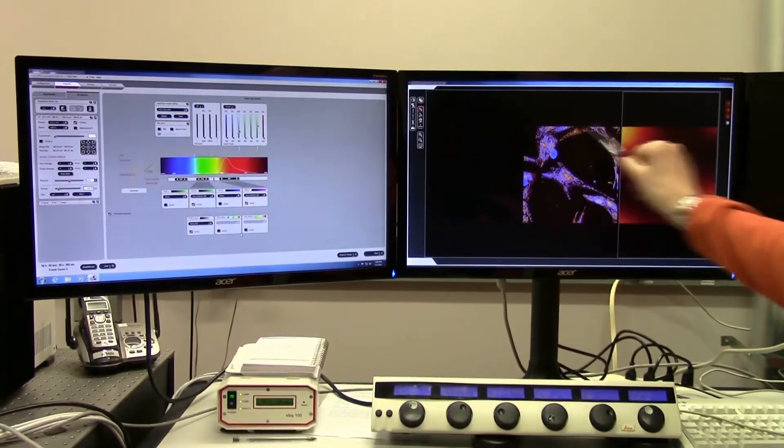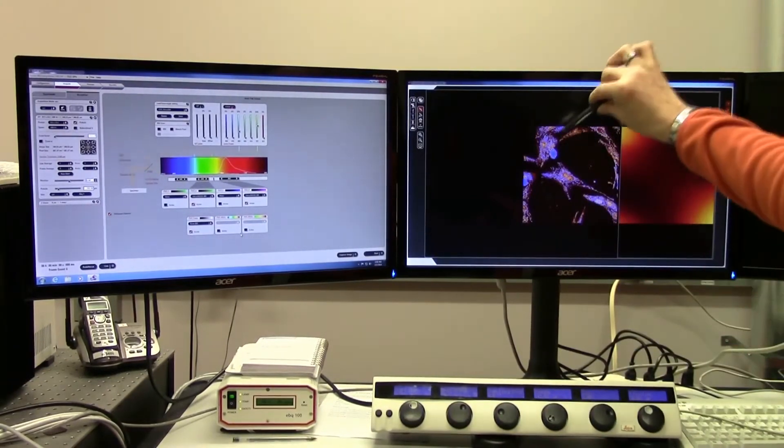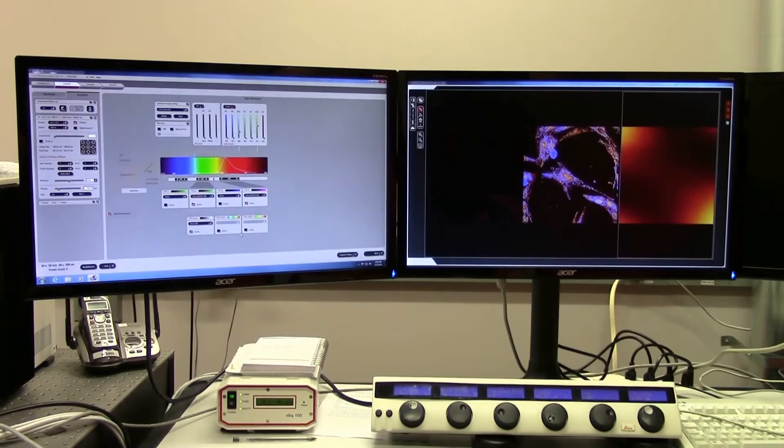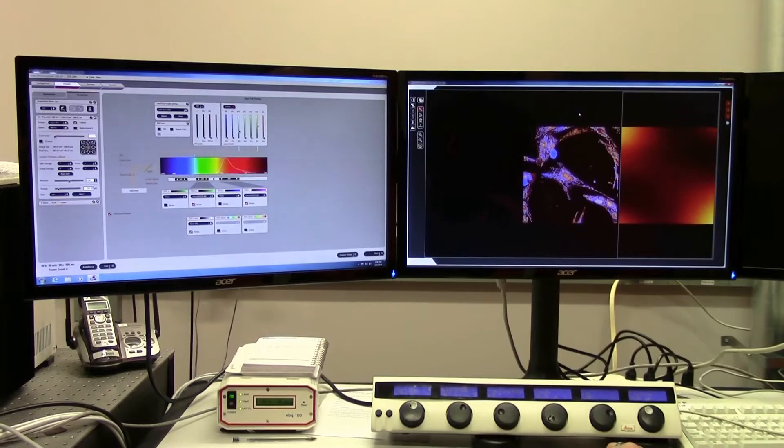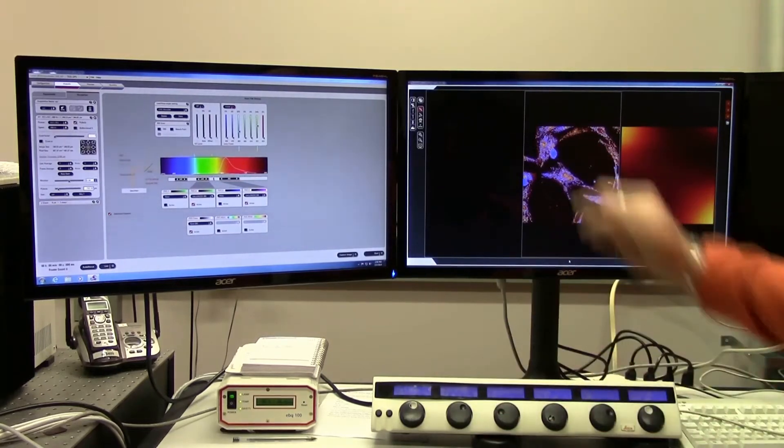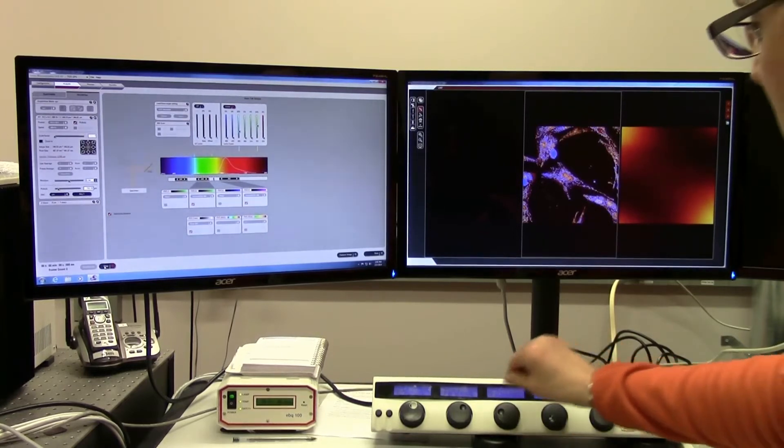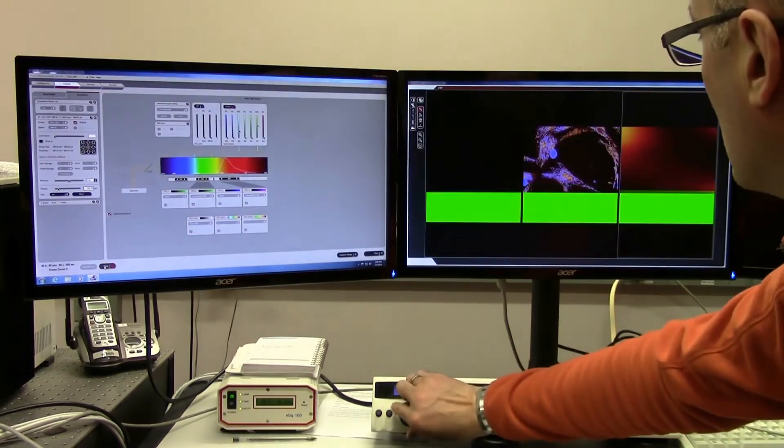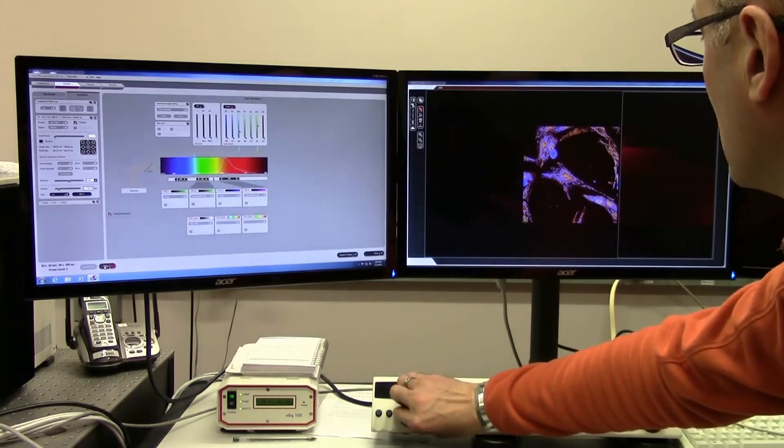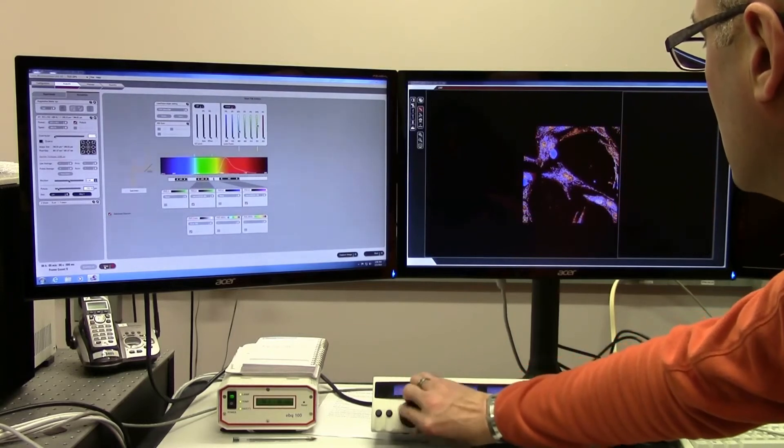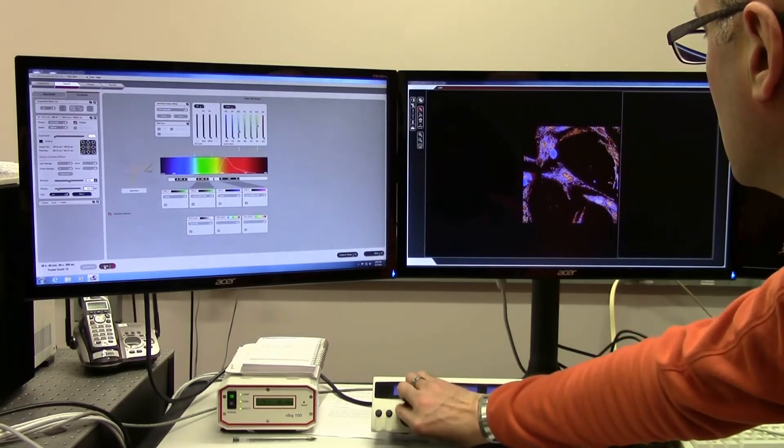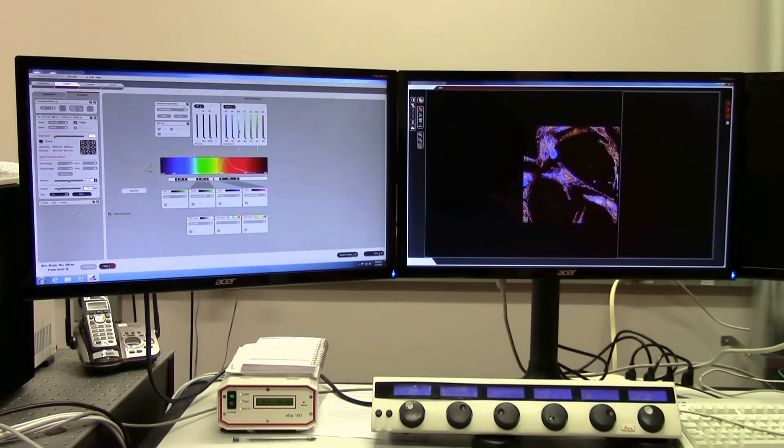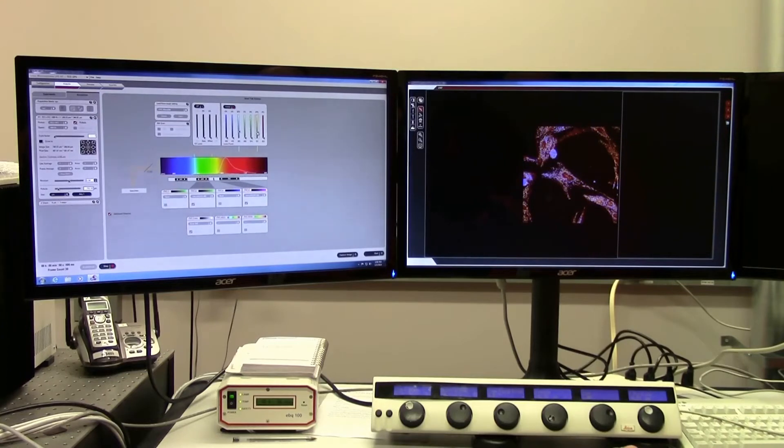What you can see from this multi-channel image is that our red is set far too high on gain. We're going to take just that channel, which means we're going to click on the channel. Now our gain settings will only affect that channel, and we're going to commence a live scan. I'm going to turn down the gain on the red channel, which still looks far too high, so I'm going to have to turn down the laser line considerably.